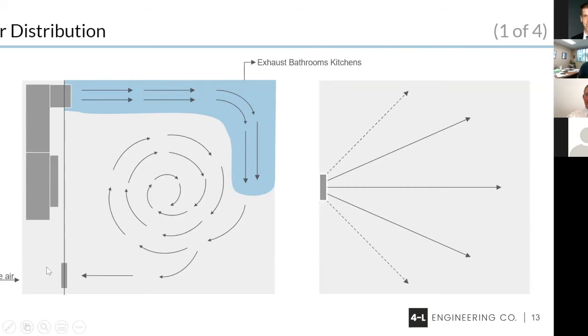Air distribution from the ceiling is shown on the right-hand slide. So we try to cover all areas of a room with this air as we blow it out. In the future, you'll hear me talk about having return air grills on the opposite side of the room so that the air moves one way across the room. It doesn't return back across the room. Next slide.